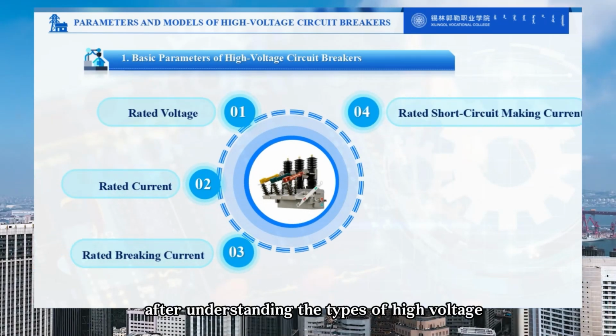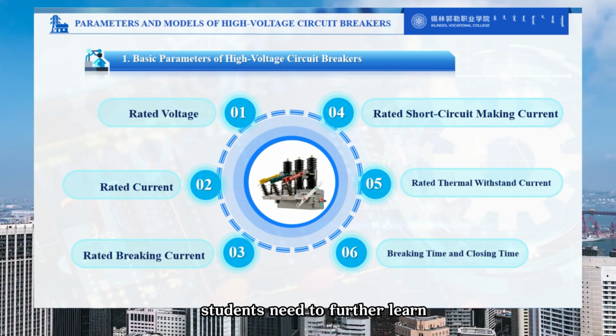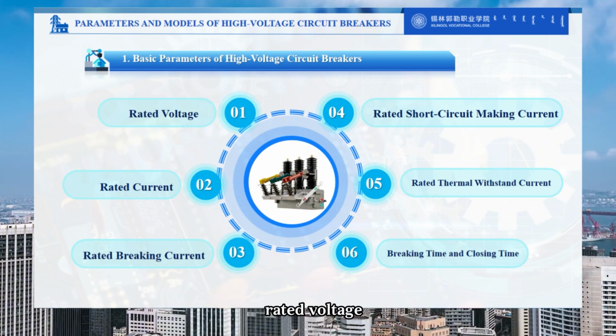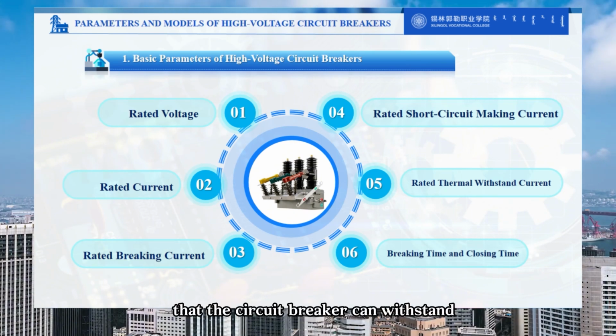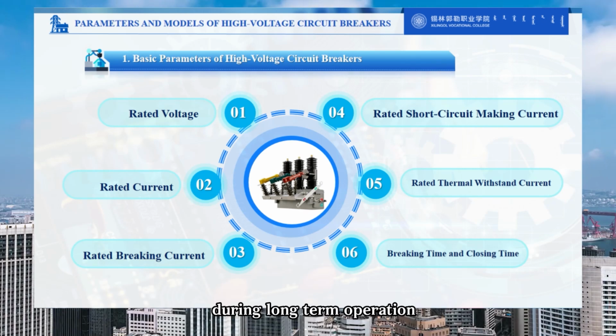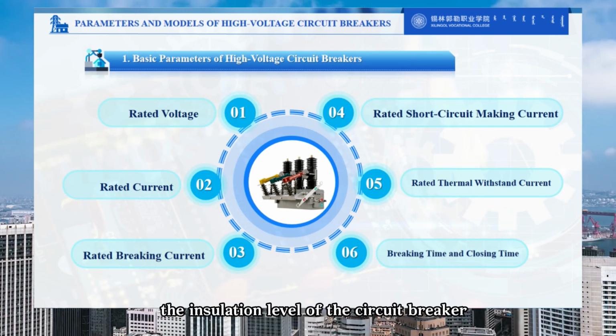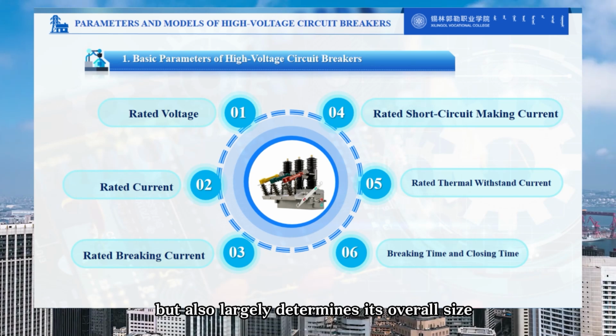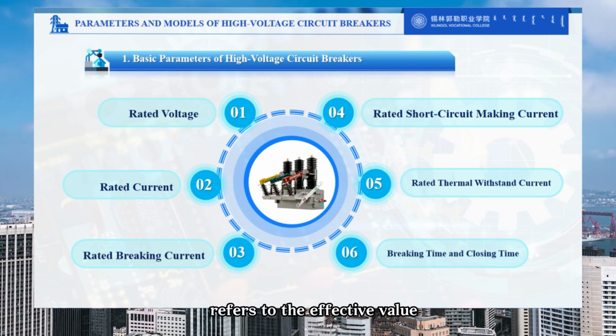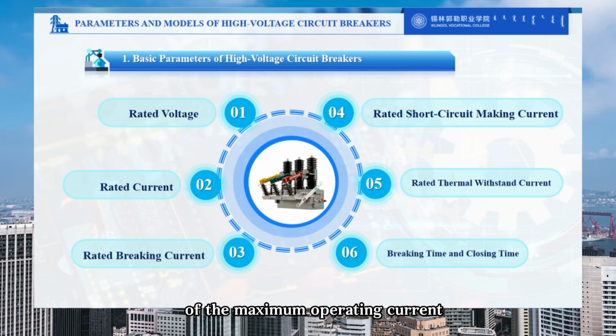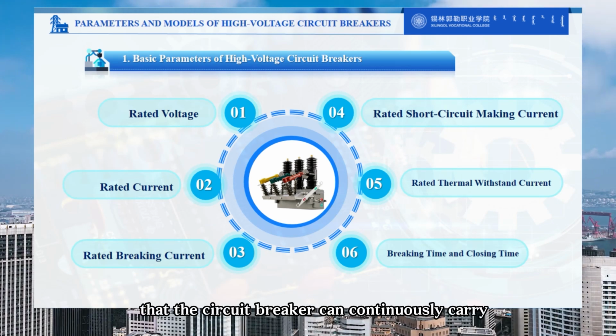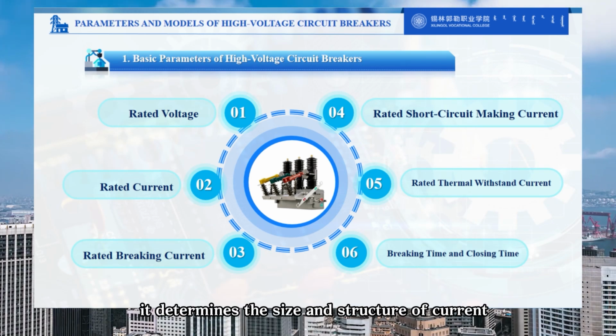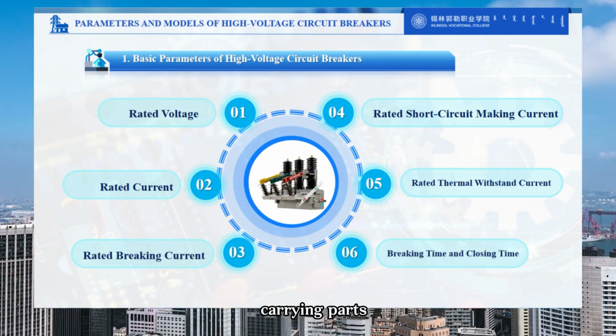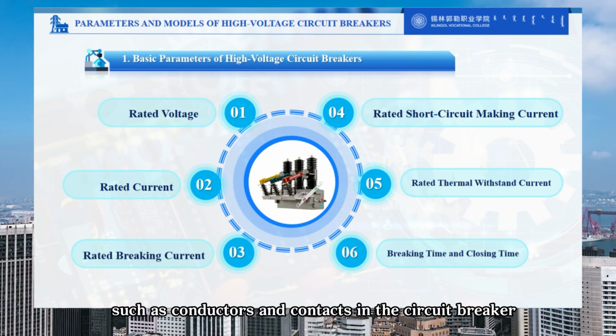After understanding the types of high-voltage circuit breakers, students need to further learn how to recognize their parameters and representation methods to know how to use them in practice. Among the parameters, rated voltage refers to the normal operating voltage that the circuit breaker can withstand during long-term operation. It not only determines the insulation level of the circuit breaker but also largely determines its overall size. Rated current refers to the effective value of the maximum operating current that the circuit breaker can continuously carry under specified environmental temperature. It determines the size and structure of current-carrying parts, such as conductors and contacts in the circuit breaker.